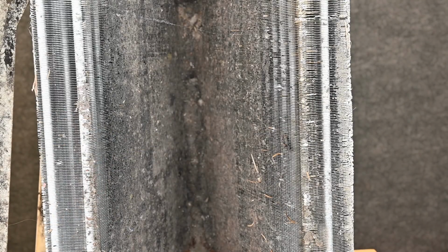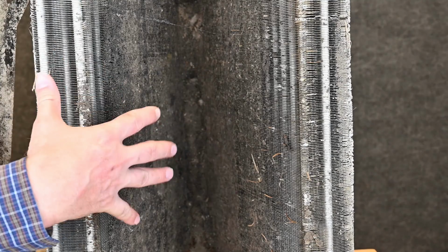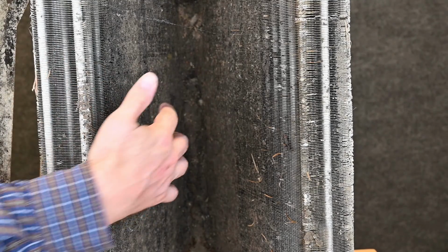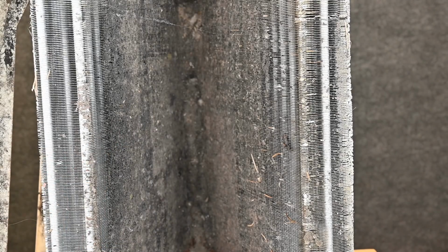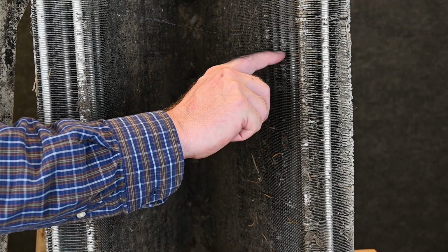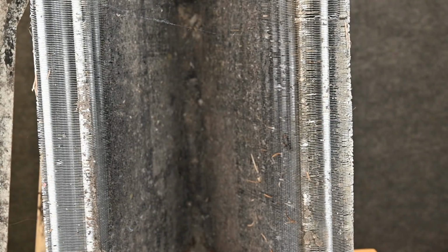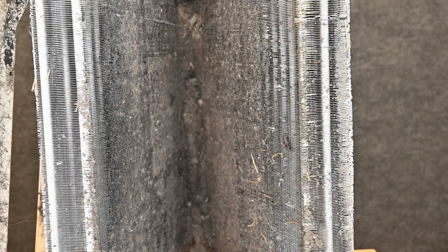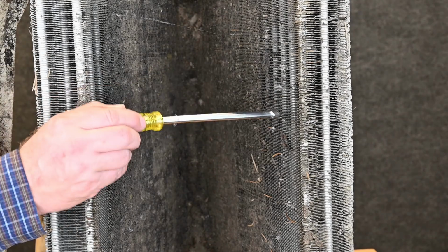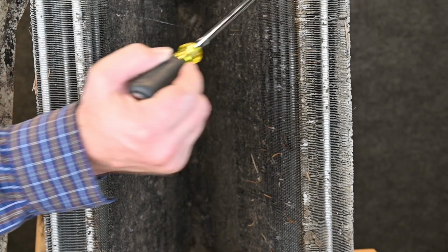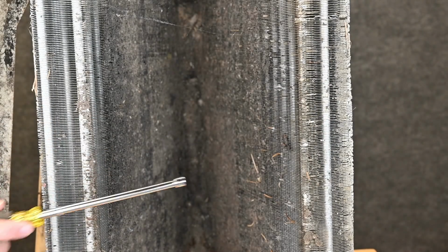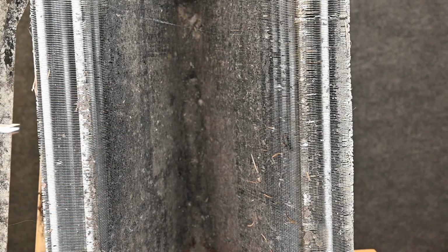So you have to be careful, because I've seen a lot of people try to clean it, what they call clean it in place. They'll leave the whole system hooked up and try to scrape this stuff off. And what it usually does is cause more problems. It will damage these fins, and really what they do is shove the dirt farther up inside the coil. So I try to look for signs to see if somebody's cleaned it in place before, because then I want to go further in my diagnostic. When they've tried to clean it in place, now you're going to have to take a light and shine it through this coil and look on the other side to see how much light you're getting through. So when you clean it in place, it can be a much bigger issue.